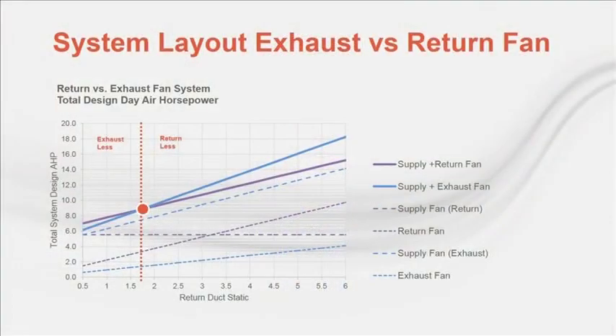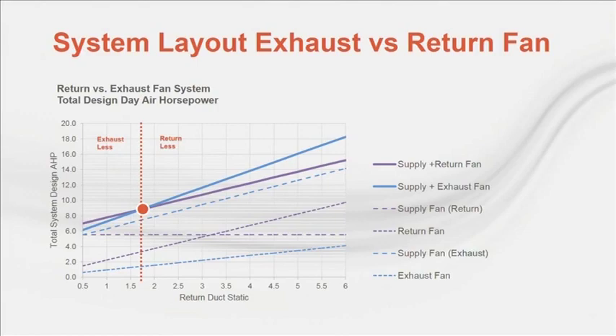Depending on the percent outside air, results may differ. In this example, the crossover point on air horsepower — the total power required from the fans — is approximately 1.75 inches external static pressure on the return duct. This means that at 1.75 inches and above, a return fan system requires less power from the fans. This crossover point will vary based on fan power requirements, which depends on how efficient each fan is and the operating point on that fan.